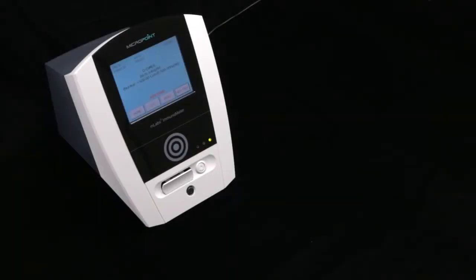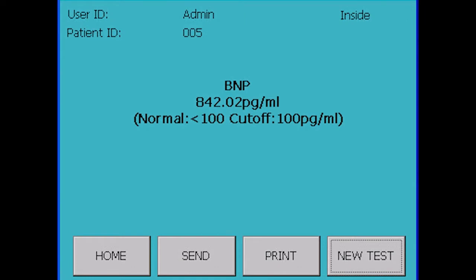When the test is completed, the cartridge holder will eject automatically. The test results will be displayed on the screen and saved automatically. Results will automatically be printed if the MLabs ImmunoMeter is configured for automatic printing. If the printer's mode is set to manual, tap Print to print the results.